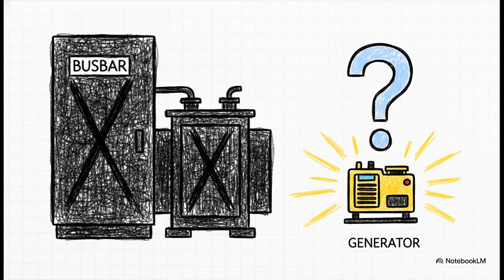Okay, so we know how the power flows normally, but let's pivot back to that nightmare total blackout scenario we talked about. The 11 kV bus bar goes completely dead. The transformers have absolutely nothing to step down. Everything goes dark. So what is the actual engineering genius behind having that seemingly tiny 1,700 kilowatt emergency generator?